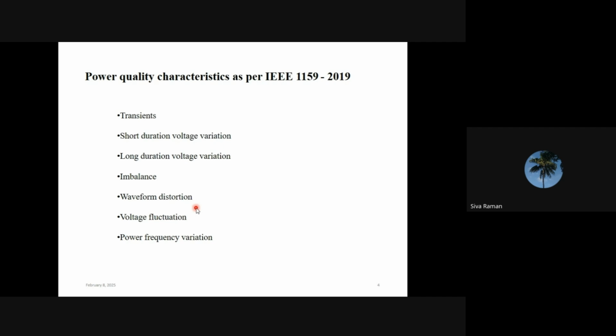So about the power quality characteristics, as per IEEE standard 1159, the latest version was published in 2019. As per this standard, the power quality characteristics are transient, short duration voltage variation, long duration voltage variation, imbalance or unbalance, waveform distortion, voltage fluctuation, and power frequency variation. So these are the seven major categories of power quality problems. The harmonics come under waveform distortion.